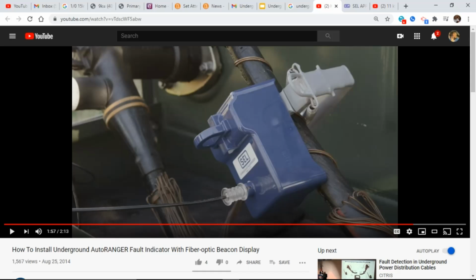All right. How does a fault indicator work? Let's step back to that again. What is it measuring? Magnetic field. The electromagnetic field from fault current. So if a fault travels through the cable in either direction, either this direction or this direction, where is it traveling to? Now I say direction of cable. Where's the fault eventually going? Is it phase to phase or phase to ground? Phase to ground. Phase to ground. So really what he's got in this situation where it's sitting right here, and we did not do this practice, is if I have fault current going from the phase into ground, he's actually canceling what the fault indicator is meant to do.